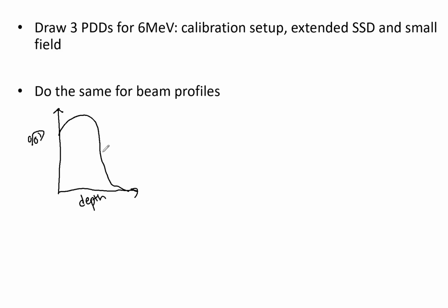So now let's talk about the extended SSD. Here, this may start just a little below, I mean, barely below the surface dose of the percent depth dose at 100 SSD. But what you're going to notice is it's going to travel farther out like this, as you can see. And then it's going to have a similar slope drop and kind of diverge there at the end and meet with the 100%. So that is what an extended SSD, and specifically, I modeled that around 115 cm SSD.